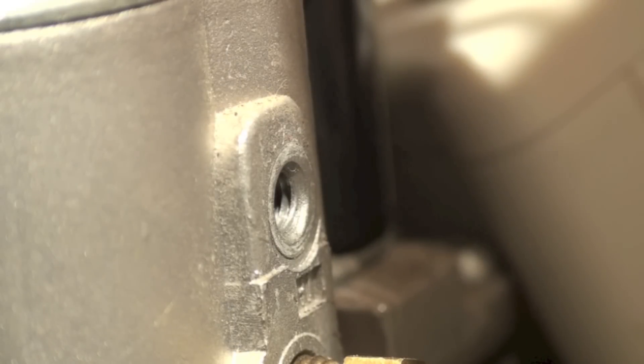Okay, if you look really close you can see inside there there's a little allen head inside there. And when you adjust it, just like any other regulator, clockwise increases pressure, counterclockwise decreases pressure. So that's the White Rodgers valve on the GUA model Snyder general furnace.